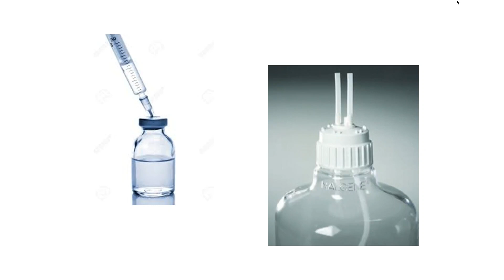And we know this for a fact because we've seen incidents where the blood going into the dialyzer is different in consistency and color than the blood coming out of the dialyzer. The blood coming out of the dialyzer was so hemoconcentrated that it looked almost black. And that was because there was a leak in the ultrafiltration system that actually failed during test, but the staff didn't want to change the machine. No alarms. But the patient hyper ultrafiltered because they chose to ignore the signs of the machine needing to be attended. And that's it.